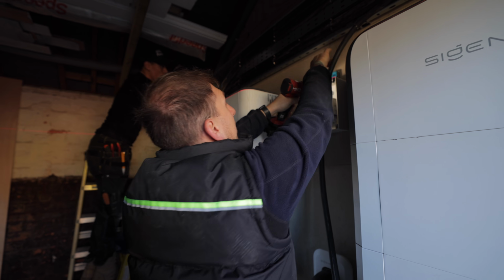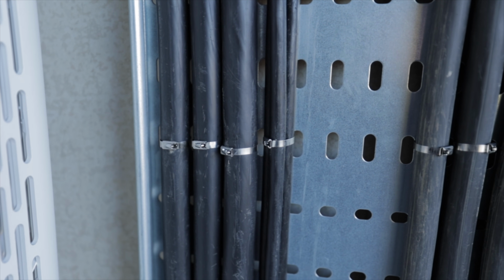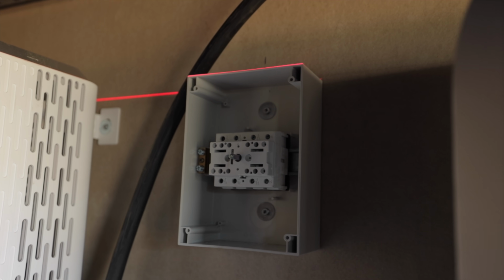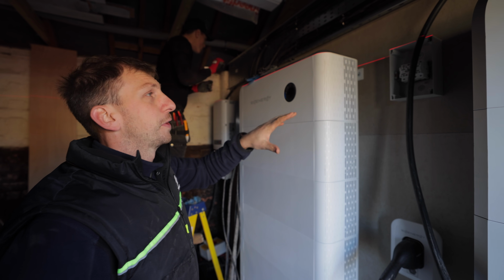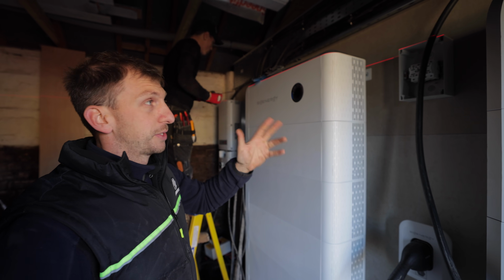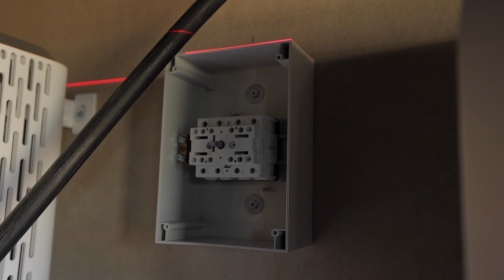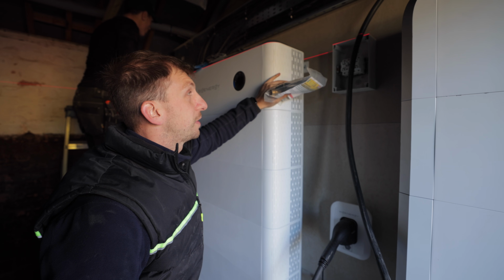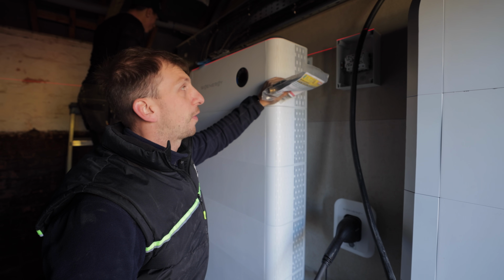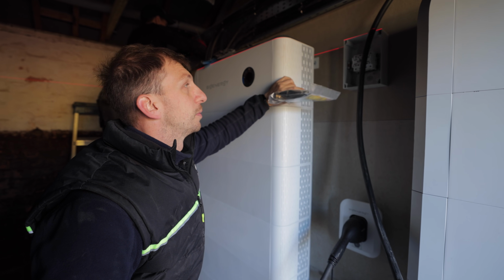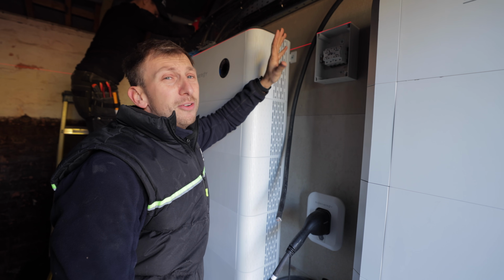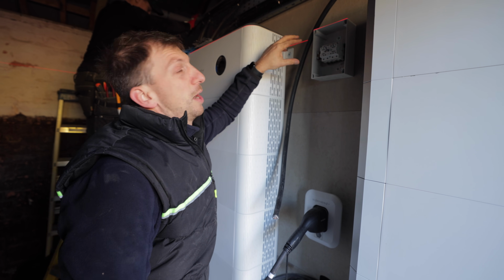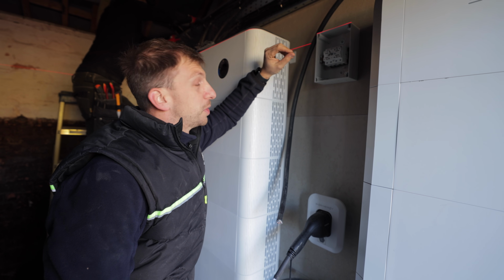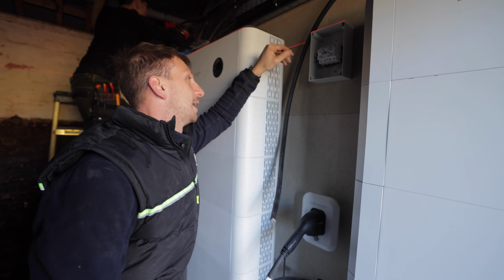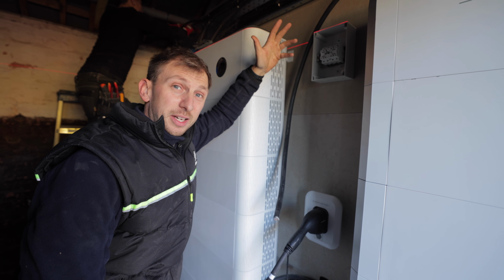So the cables are getting all dressed in now, we're more or less there with all of them. Once they're all dressed in, we're going to bring each inverter's AC supply down next to it on the left-hand side and terminate them in an AC isolator. We've gone for the 63 amp 4-pole isolators. With the 63 amp, they're slightly oversized, which is great for bigger cables, giving a bit more room rather than fighting to get bends and sweeps in. Some of you might look at this isolator and think I've screwed through the back of it - well, it's being mounted indoors, so we're not concerned about IP or water getting in, so in all honesty I don't care.